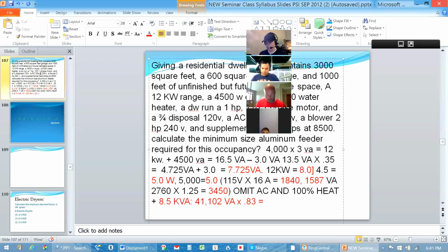But I'm looking at taking this 41102 and multiplying it times 0.83. What that does is it reduces the service value to a value that's now the equal standard of what a commercial building would be. In other words, a wire in a residential dwelling is worth more there than it would be in a commercial setting. Excuse me, I said that backwards. A commercial wire would be worth more in residential service. A service residential wire would be worth less in a commercial building. So we're lessening this residential wire so we can get the equivalent of what you're looking at on page 161. So I'm going to take that times 0.83, and that's going to give me 34,115 as an adjusted volt amps for that residential feeder. Is there any question on what I just did or what I just said?